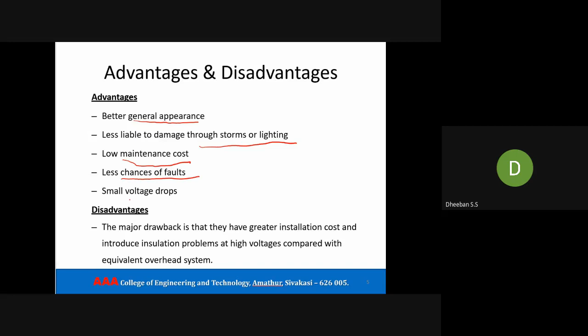Moving on to the advantages and disadvantages of cables. The primary advantage is its general appearance. It has a very good general appearance. From the protection point of view, it is less prone to damage from storms or lightning than your overhead line. In an overhead line, the installation cost will be less but the maintenance cost will be high. In the case of underground cables, it is just the reciprocal of it. The chance of a fault is very low, and the voltage drop, which occurs as a loss, is also very minimal. The main disadvantage, as I said, is the greater installation cost. The installation required is very high.